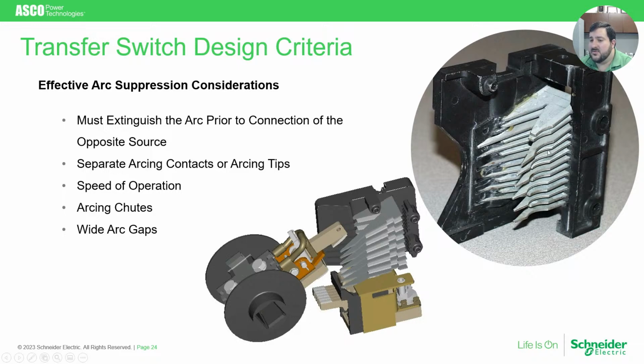The conductive nature and electromagnetic nature of these sheets pulls the arc away from the arcing contact, expanding it over a greater distance and area and cooling it down, which leads to the arc collapsing and ending the arcing condition and event more quickly. So the main point of the arcing contact is, again, to help very quickly extinguish that arc, because the arc is one of the areas, whenever you're doing any kind of switching, that leads to most of the wear and tear on contacts and equipment. So it really helps reduce the duration and intensity of that arc overall.